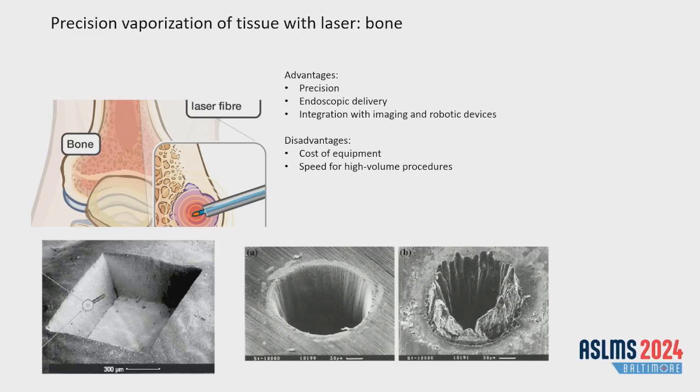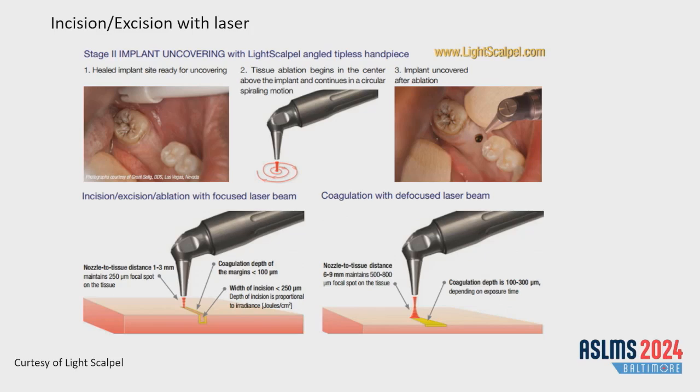And by controlling the parameters of the beam, you can dial what you want to do. More ablation, less coagulation, or if you need to stop bleeding, then you can actually defocus the beam and go to more of a coagulative effect.